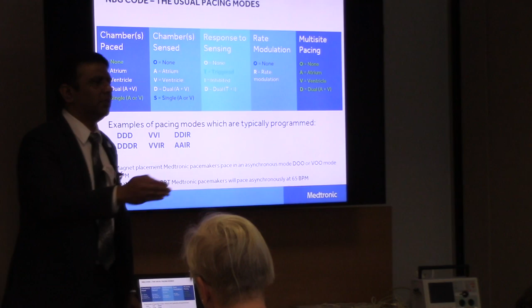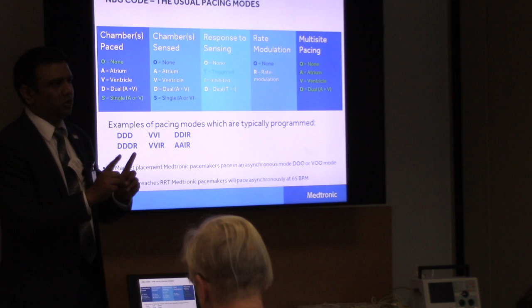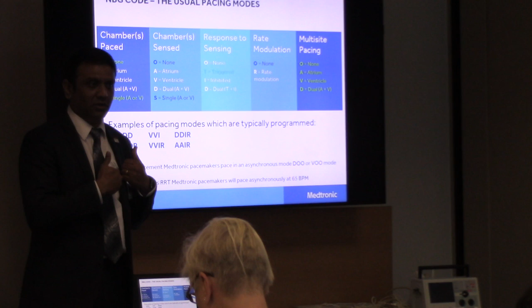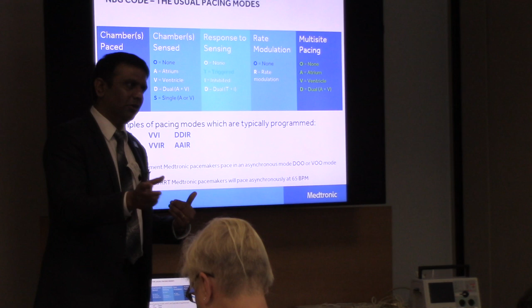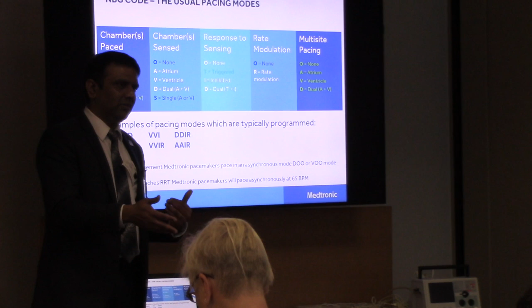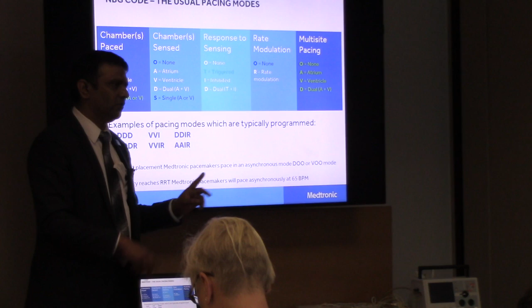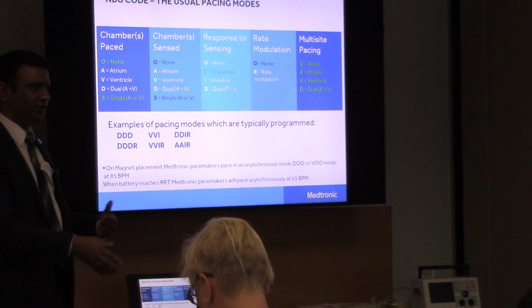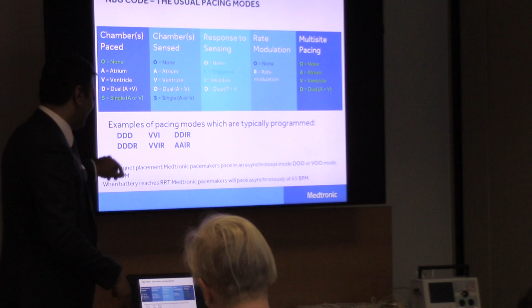But if they don't have intact conduction, and some people are not always in a heart block. They go frequently or occasionally in and out of heart block. So for those patients, you would have to set the AV delay appropriately so that they're not pacing all the time. If you kept too short of an AV delay, they're going to keep pacing all the time because their intrinsic AV delay is at 200. And if I set their paced AV or sensed AV below 200, they're going to be pacing irrespective, all the time, because that AV delay is crucial in determining whether they will be paced or not. So in the DDD mode, all those things come into play. Okay, remember that AV delay comes into play. If you want more explanation, you'll have to do a separate course on that.